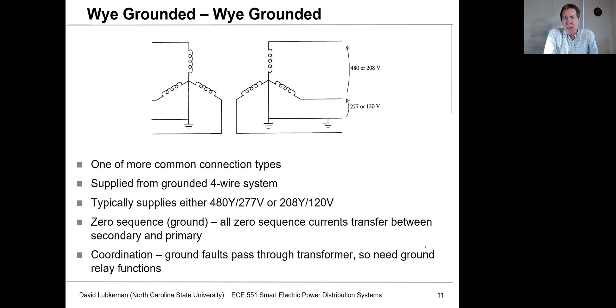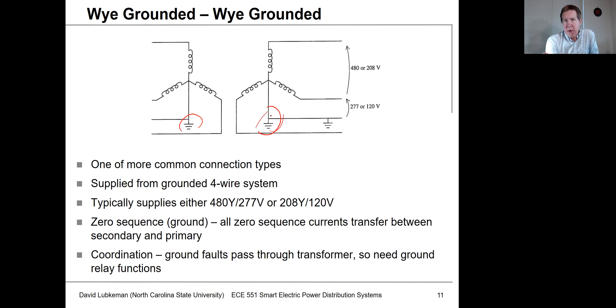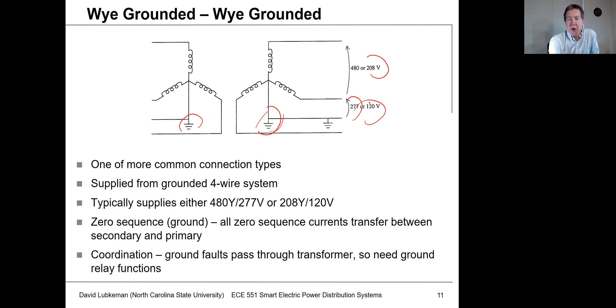The Y-ground/Y-ground connection is very common. If you're going to supply industrial load at 480 volts or commercial load at 208 volts line, this is likely the transformer connection you'll see. Both sides have solidly grounded windings. On the secondary side you're making the ground for the customer — 480 volts line corresponds to 277 volts line-to-neutral, or for commercial load, 208 volts line corresponds to 120 volts. If there's a fault on the secondary side, you'll see a neutral current on the primary side.